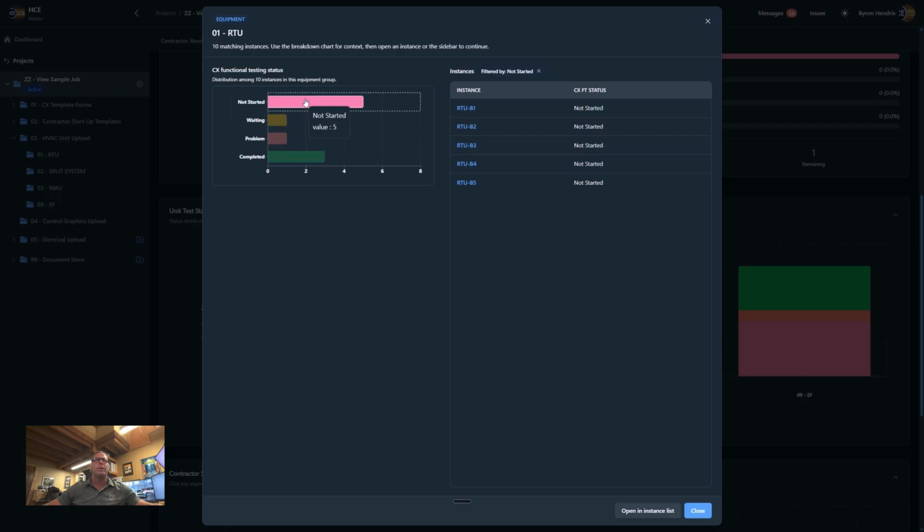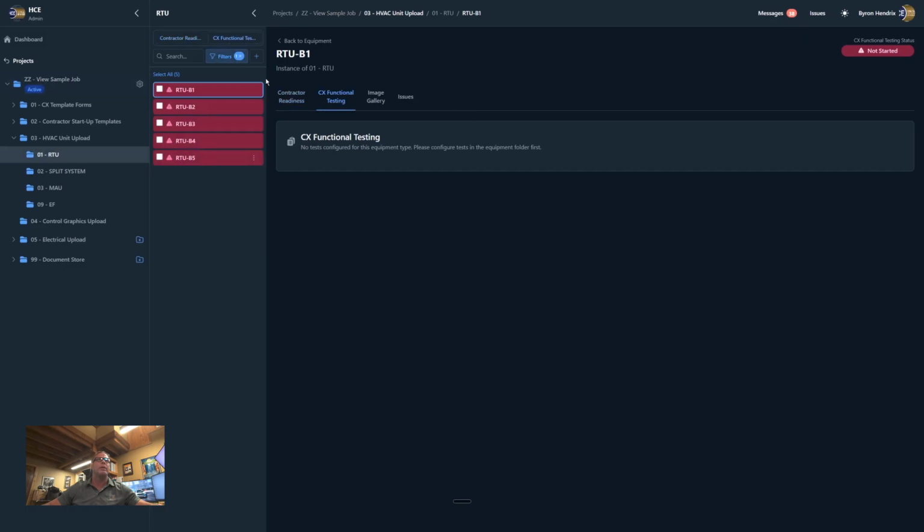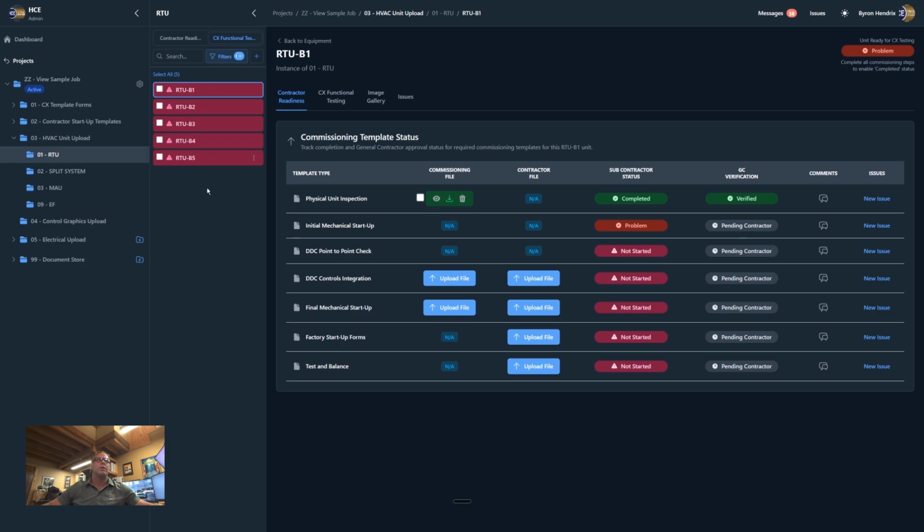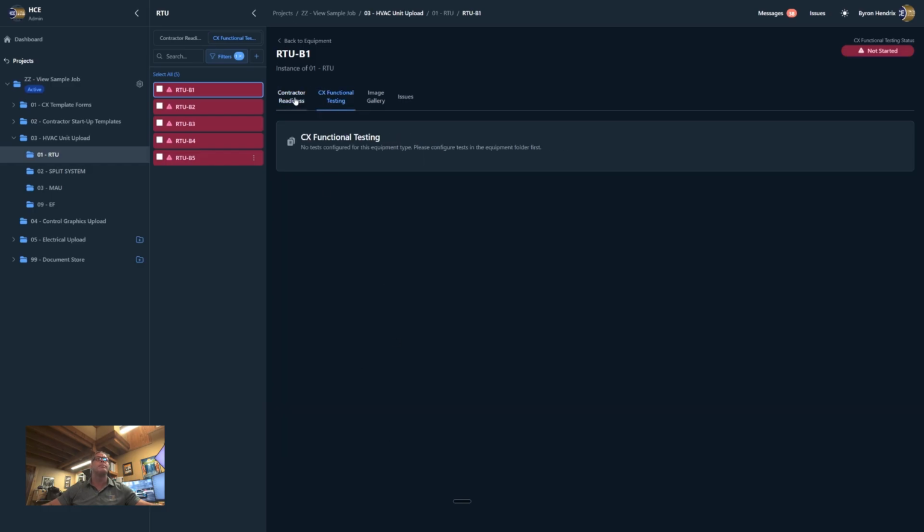And anywhere here we can see, well, what are we not tested? Well, we haven't tested area B. And why didn't we test area B? Well, if we go back and look, they're not ready. So we can't test it because the contractor readiness shows they're not ready. Therefore, no testing's been done.